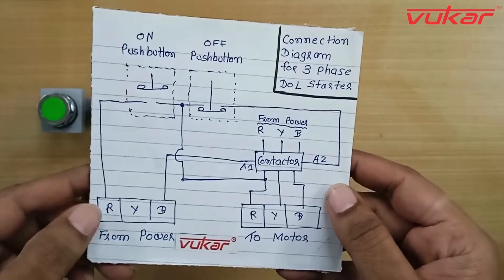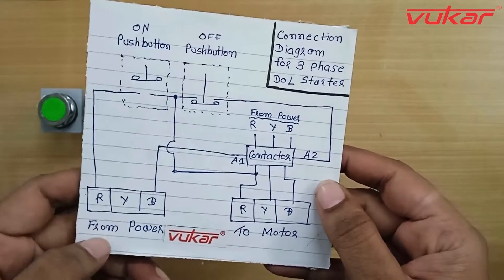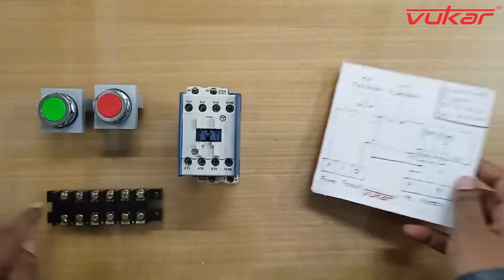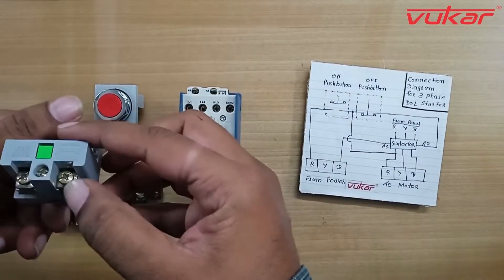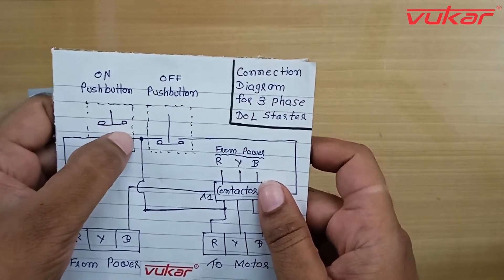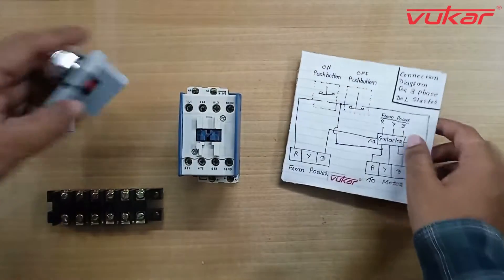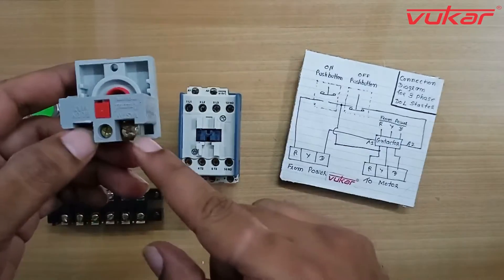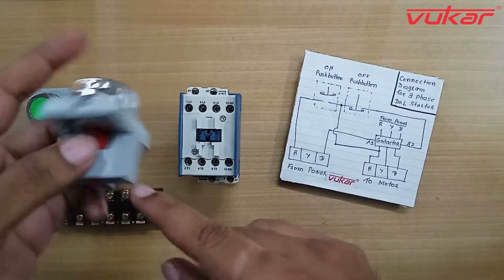Now we will see the connection of control wiring. So input R is connected with on-push button. The other point of the on-push button is connected with off-push button and other point of off-push button is directly connected with contactor coil A1 terminal.